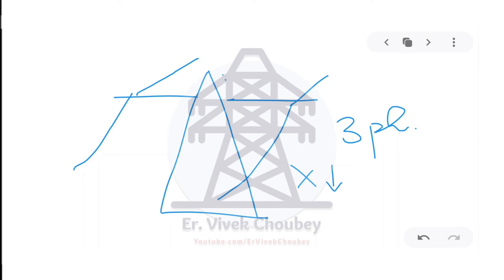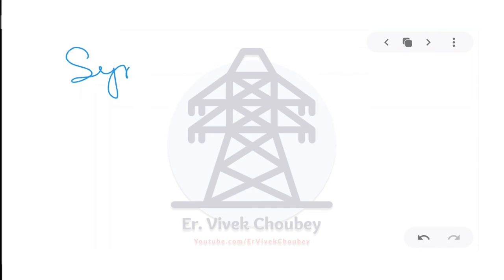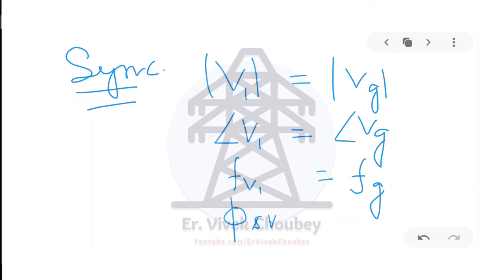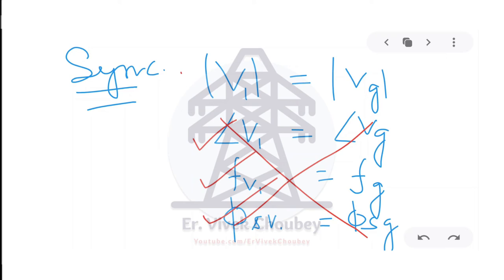Another advantage: simplified synchronization. In AC, to connect a generator to the grid you need: voltage magnitude V1 = VG, angle of V1 = angle of VG, frequency of V1 = frequency of grid, and same phase sequence — many requirements. With HVDC, none of these matter. There is no angle, no frequency, no phase to match. All you need is the same voltage magnitude. This makes the system comparatively easy and less complex.